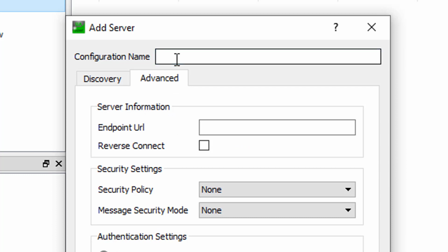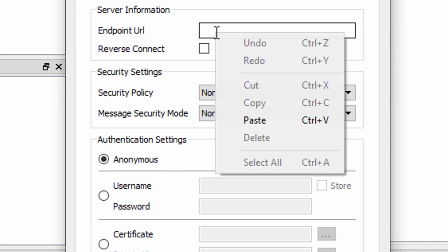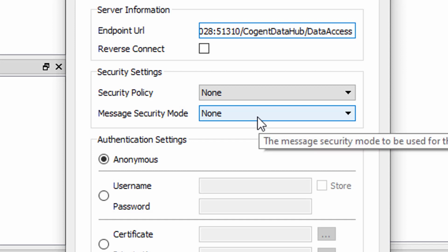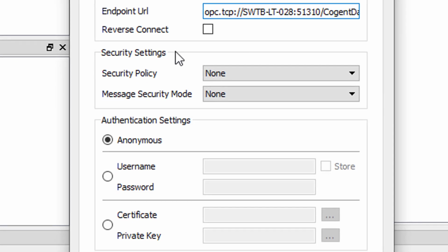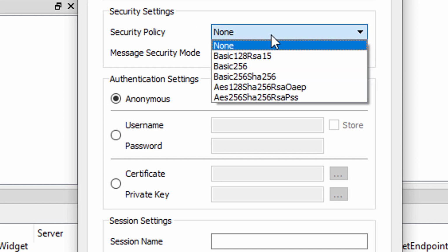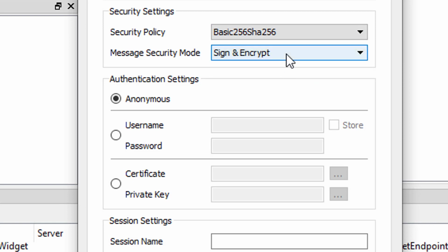So I'm going to name my configuration DataHub UA. Then I'll enter the endpoint URL to match what we saw in DataHub. Since I copied it earlier, I can simply right-click and paste to ensure accuracy. And as you can see, it did paste in my endpoint URL from DataHub that I copied earlier. Next, we need to select the security policy and mode. So if you see the security policy options available in the UA Expert, we can actually select any of the first four options in this list.